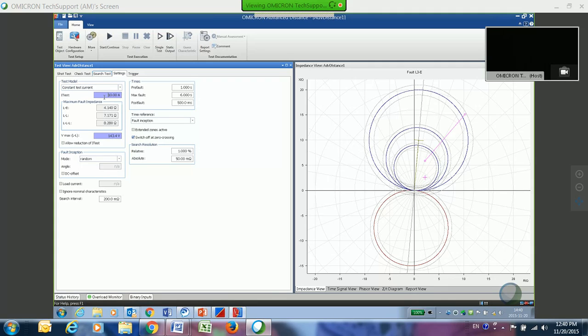And then you can specify your I test. Now, one thing that you'll see here is this is actually a darker color. It's kind of got a darker background to it, maybe a purplish looking color. What that means is that it's actually linked to a value, but that doesn't mean that I have to use 10 amps as my maximum current. That I test current is typically 2 times my I nominal, which is the value that I had set up in my object file under my device XRIO function of it.